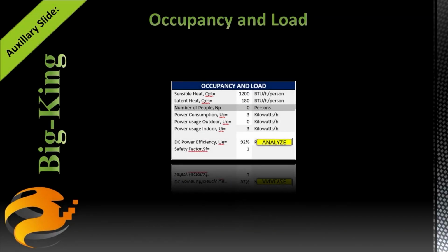In the occupancy and load section, sensible heat and latent heat are calculated here only as they pertain to persons occupying the building. These values are calculated, but not displayed as there are seldom personnel in communications shelters. Power consumption in kilowatts can be obtained from an electrical meter or derived from equipment specifications after estimating duty cycle. Typically, for communications equipment, it is assumed that 100% of electricity consumed is dispelled as heat.